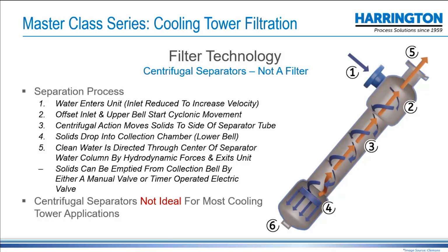The centrifugal separators, the way they work, water comes into them. It's usually pushed down to increase the velocity, like putting your thumb on a garden hose. The bell is often offset, so it starts a centrifugal action, and the high velocity water spins around the unit along with the sediments in it, and it hits a bottom plate, and then there's no baffle or tube in it. It's all hydrodynamic action. It creates a path through the center where clean water can come out. And the solids will collect in the collection bell down at the bottom.